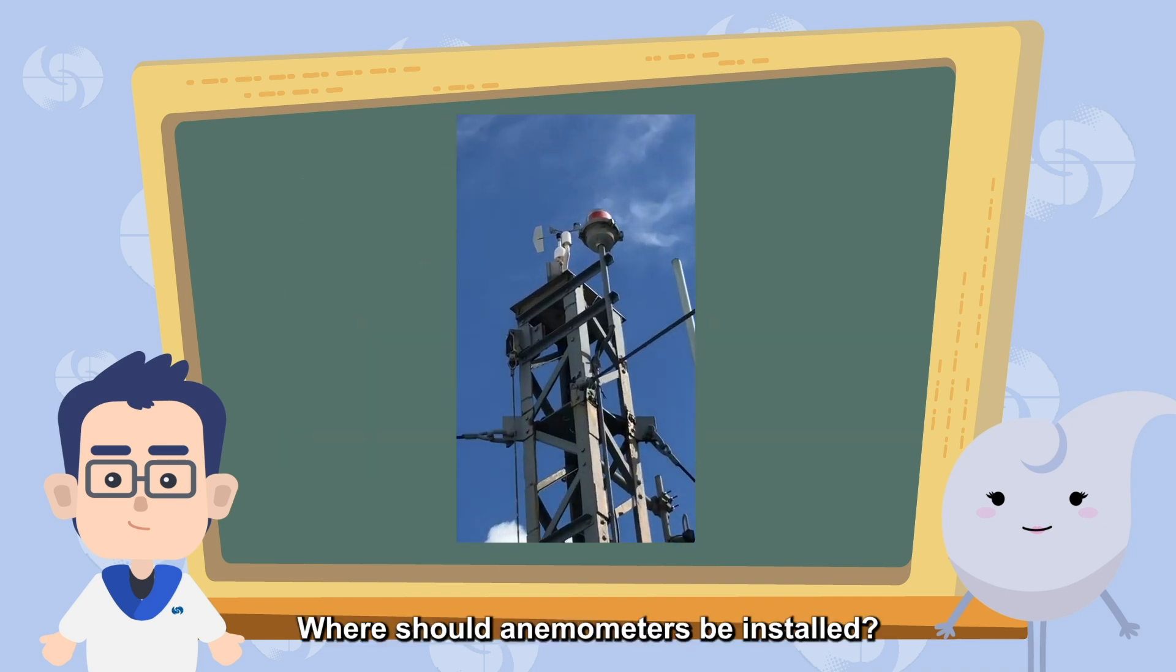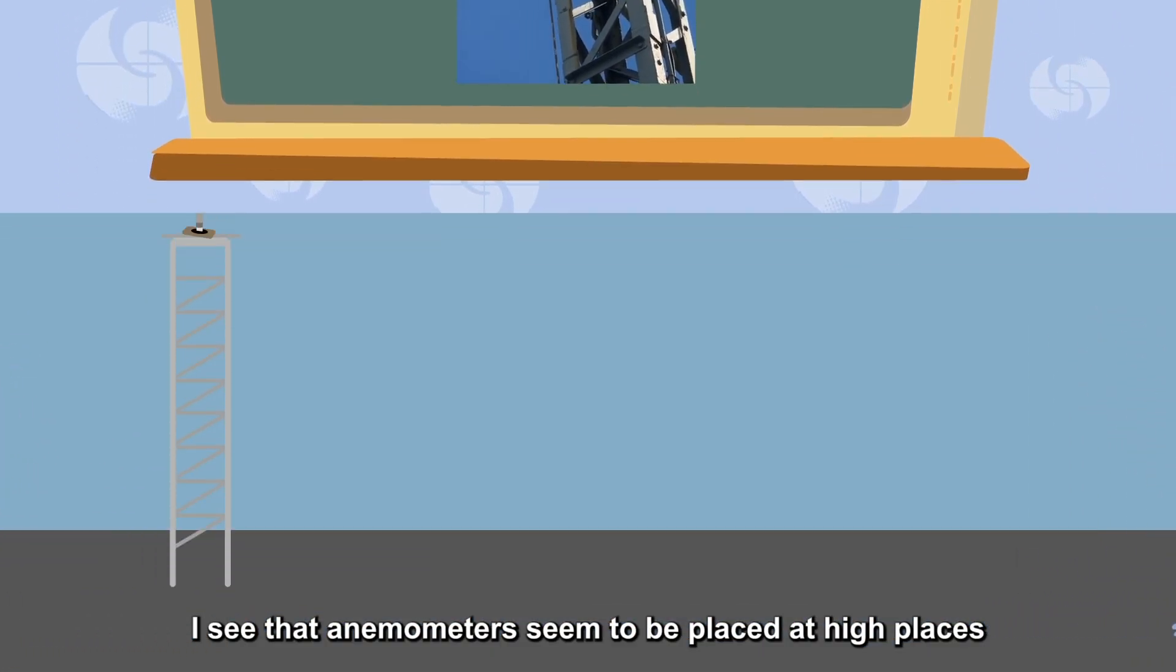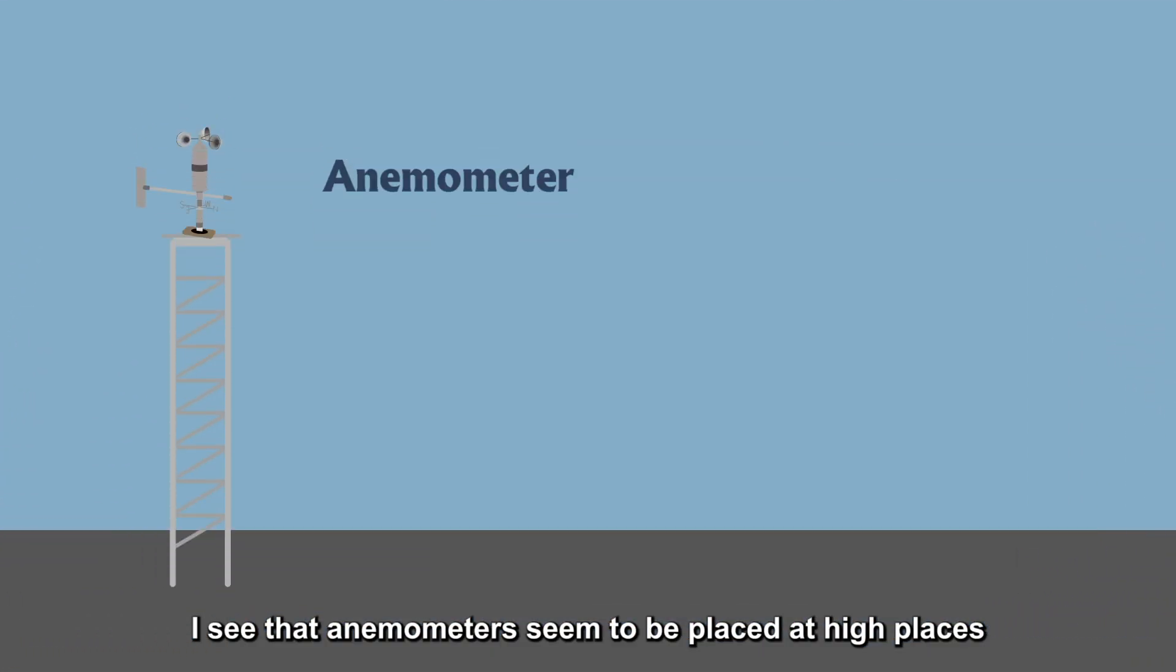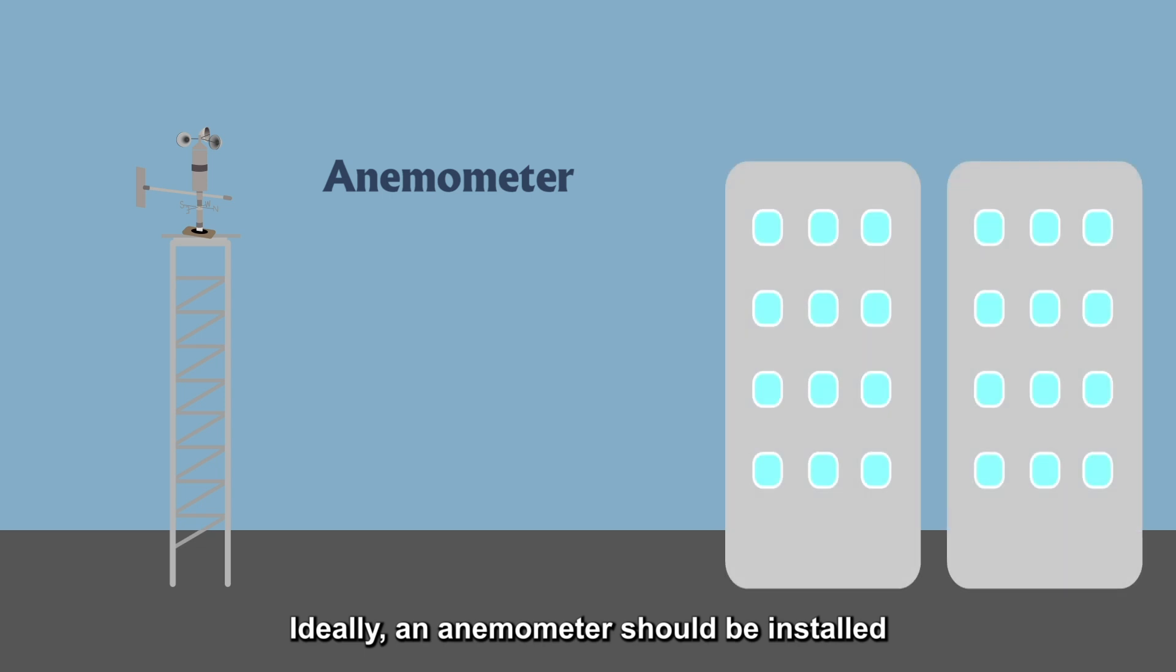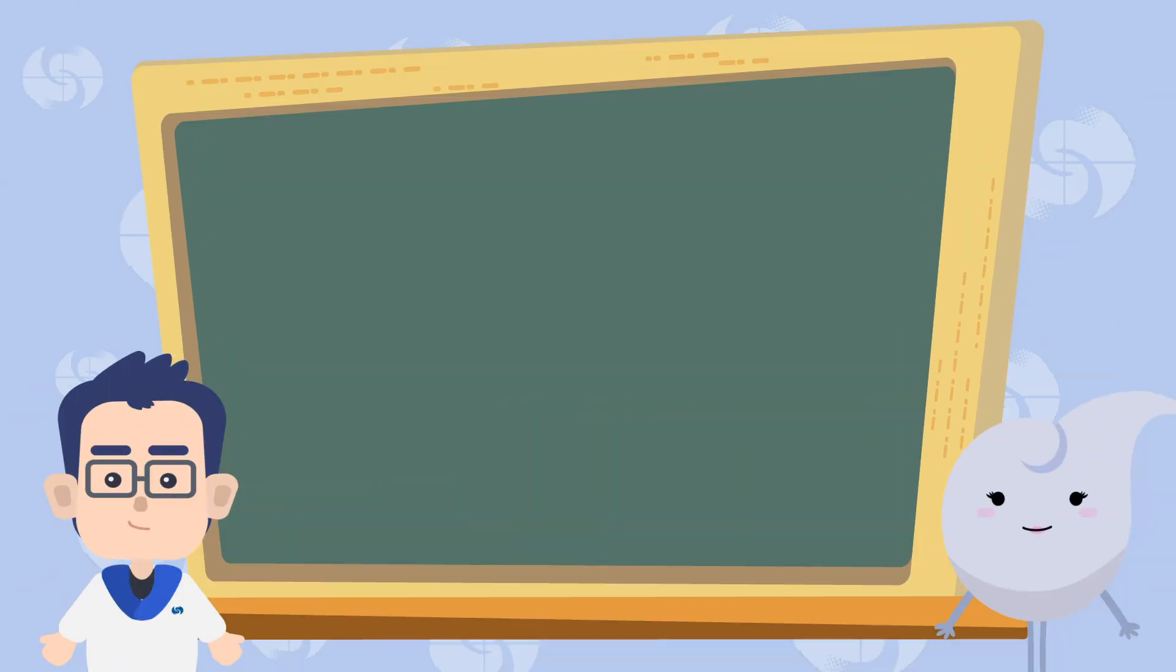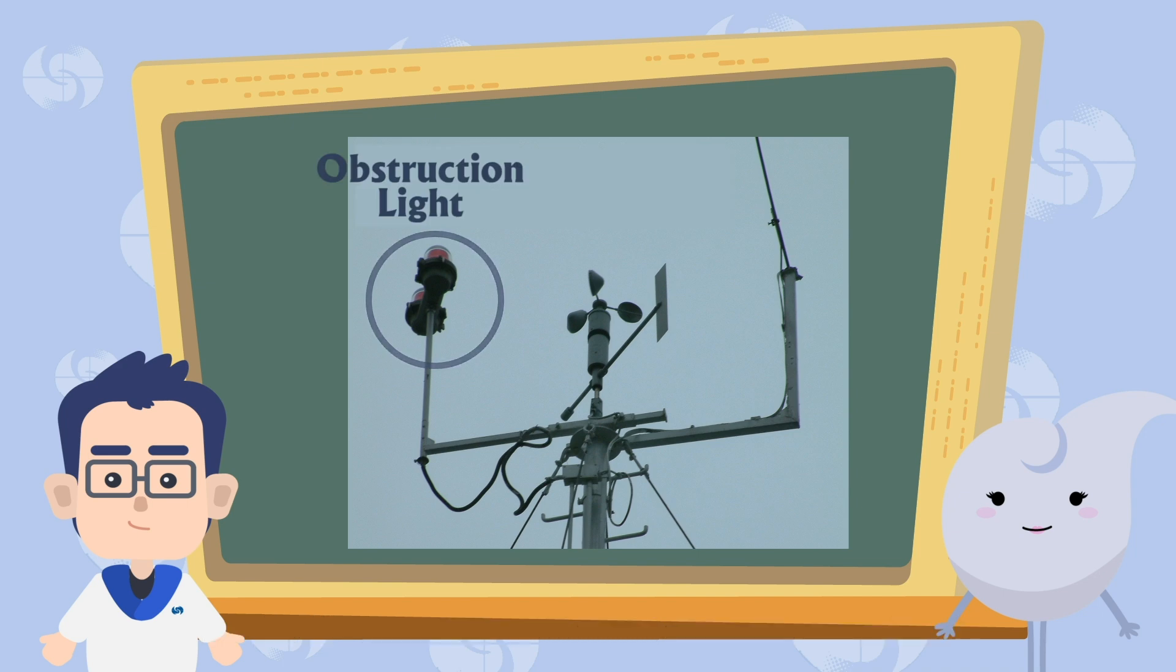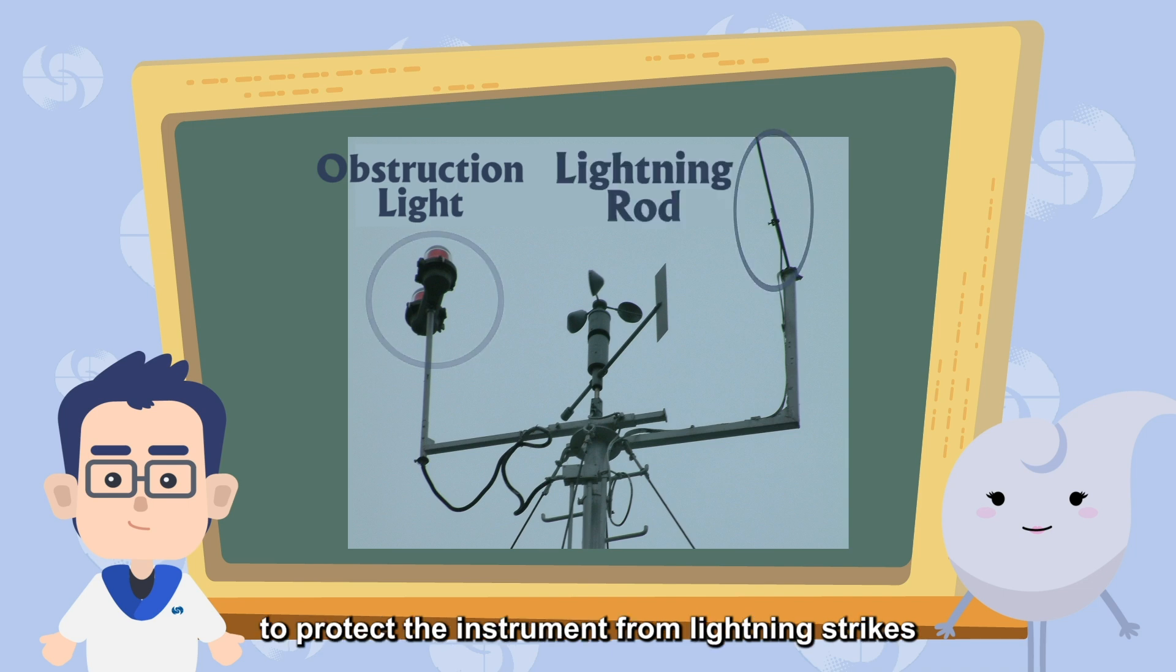Where should anemometers be installed? I see that anemometers seem to be placed at high places. Yes, there are standards for anemometer installations too. Ideally, an anemometer should be installed 10 meters above the ground, and the location should be open and unobstructed. Usually, we will set an aviation obstruction light next to the anemometer to avoid collision by an aircraft, and a lightning rod will be set on the other side to protect the instrument from lightning strikes.